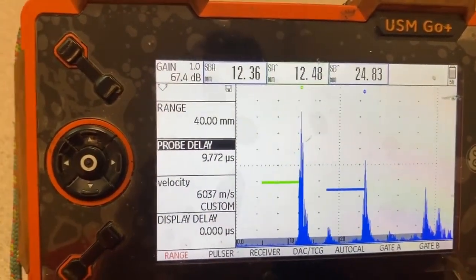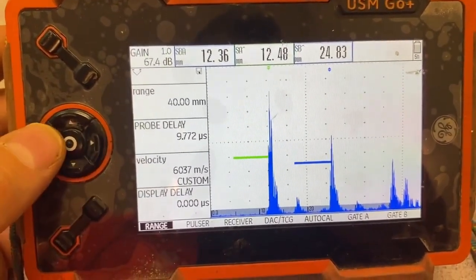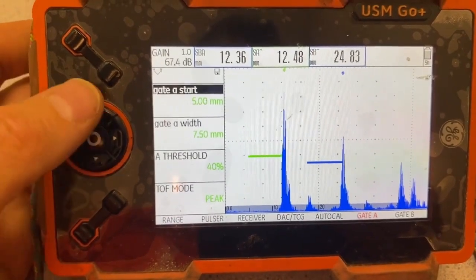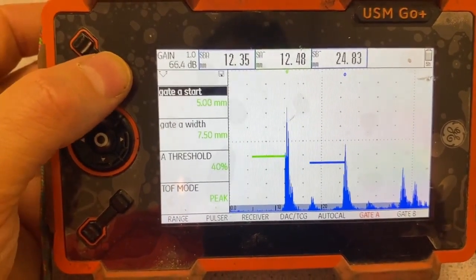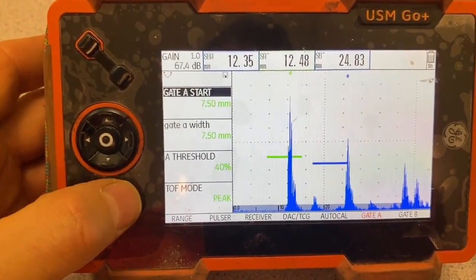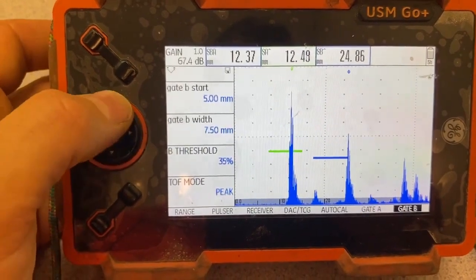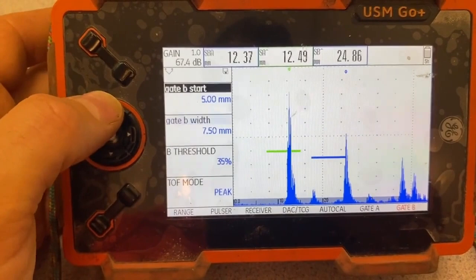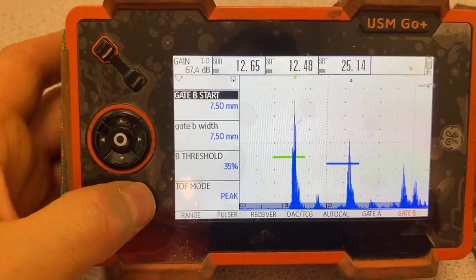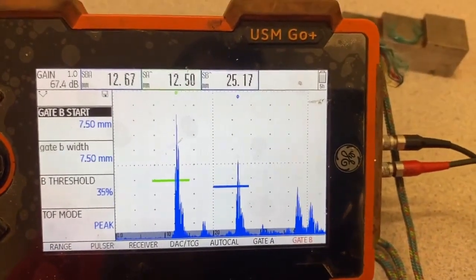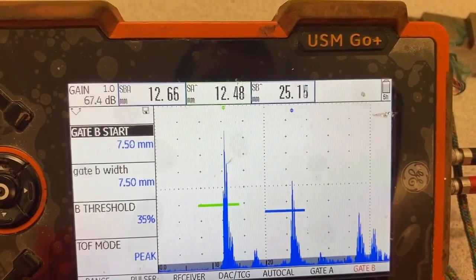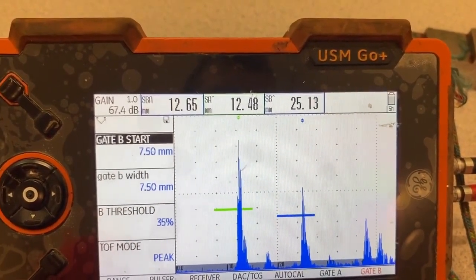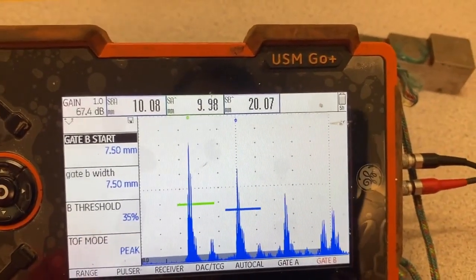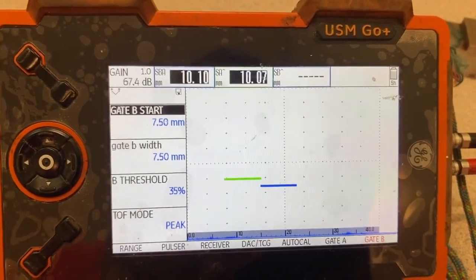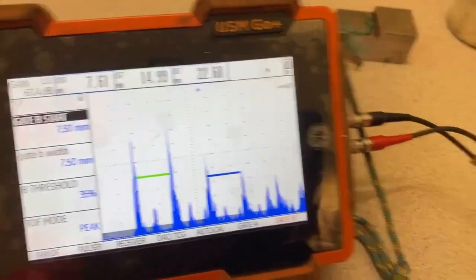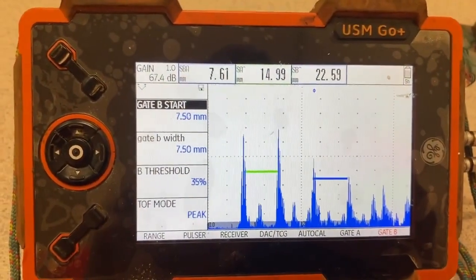Now, we need to carefully move our gate, the one we are working with, to properly see it in its correct position. We move the gate quickly now. Please proceed through this gate and also through gate B for your convenience and guidance. As I mentioned, it should pick everything on gate A and gate B. And now we will move there, and carefully check what it currently shows. It clearly shows the value of 12.6. Not so big a difference, 0.1 mm. But if you go to 10, it shows almost exactly 7.5. However, we need to carefully move the gate to properly see the precise measurement. Okay, that's it.